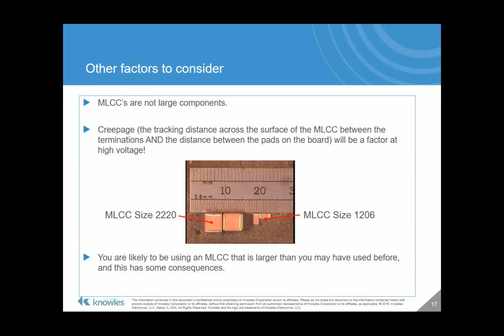So other things we've got to consider, normally multi-layers are not large components, but high voltage means you're going to get bigger. You've got to consider the creepage distance. We're going to be applying 4000 volts to this, and you need to consider the creepage and the clearances, otherwise you will get arcing occurring. So creepage, the distance across the surface of the multi-layer, and the distance between the pads on the board, so it's not just the component, will be a factor.